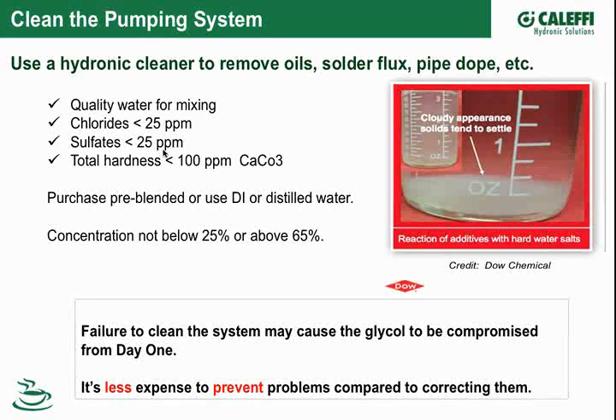That's excellent advice, because looking at that list, the only number I'd know how to test on the job is hardness. I've got a little hardness test kit, but no idea how to test for sulfates or chlorides. Some guys have TDS meters that read conductivity, but that's a good point, just assume one of those, if not all of them, is going to be out of whack.